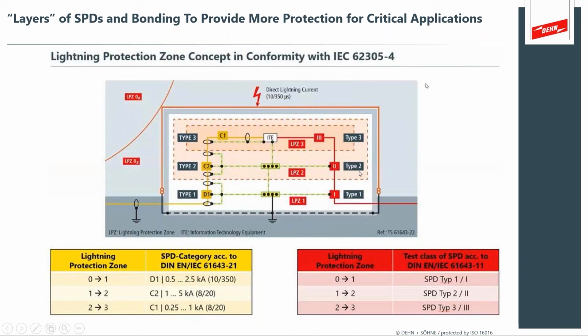So it is possible to coordinate them, and I've seen some really excellent products that provide excellent coordination with built-in mechanisms, but usually there's something like a decoupling element. We had a schematic earlier where we showed that difference between a spark gap and a silicon avalanche, and there was a series element to force the 2 to respond together. And that's really what you need to pay attention to. Yeah, so I just want to add, you can have a combined Type 1 and Type 2 device in the same package. Yes, it is absolutely possible.